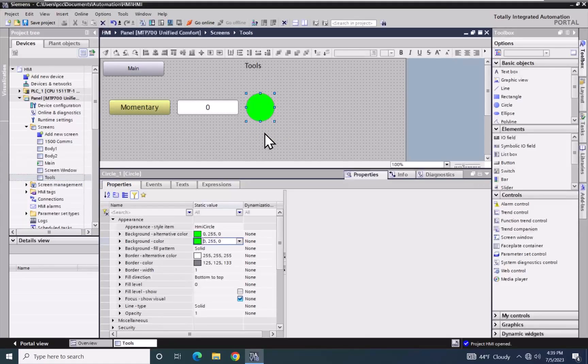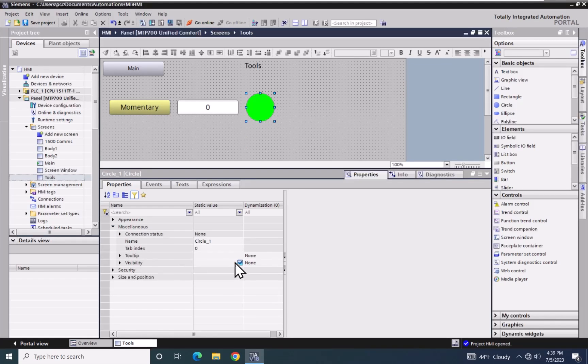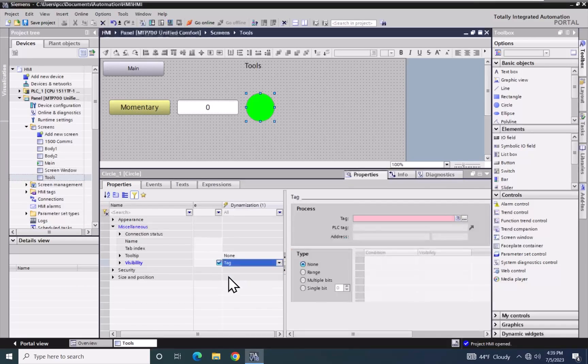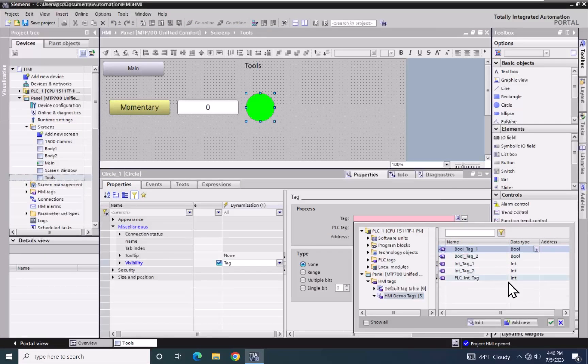When the momentary button sets bool tag underscore one, I want to make this circle object become visible. In order to control the visibility of an object, I'm going to go into the miscellaneous area, expand it out, and locate the visibility property. Currently the static value has the object checked, meaning it will always be visible during runtime. The dynamization column for visibility is set to none, so I will select none, bring up the drop down, and select tag. We're going to use the same tag used to control the background color — bool tag underscore one.